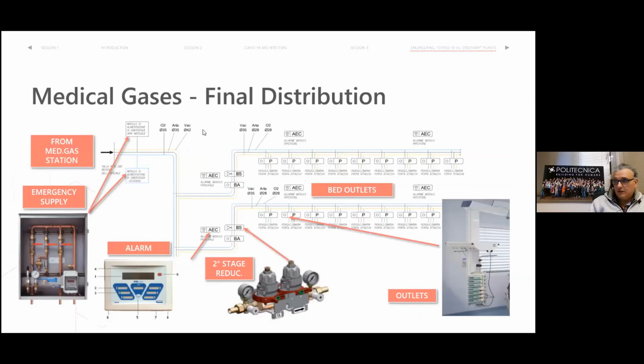And essentially, we will provide the emergency supply outside the building in a position where the truck can arrive very easily. Then we have the alarm at the entrance of the department. We have shut-off valves. Here there are the second stage pressure reducer. In Italy, we use the second stage reducer a lot. In the installation made according with British standard, or in general in the English tradition, foreign countries, they don't use the second stage reduction. Everything is made by the first stage reduction, and then there is just the distribution.